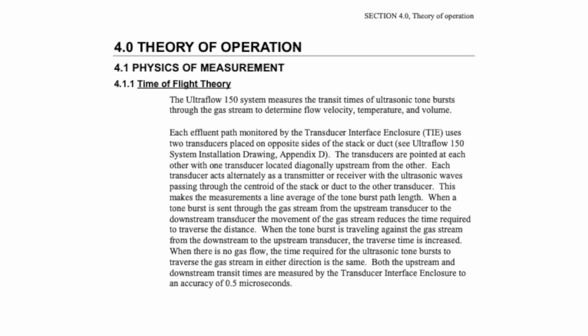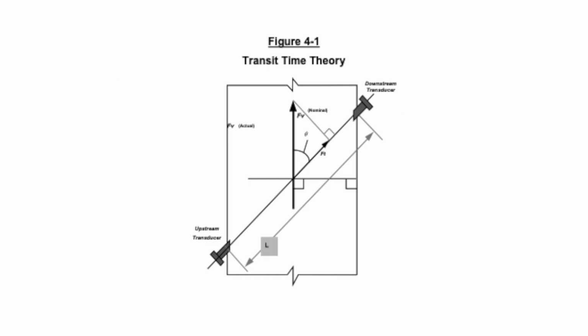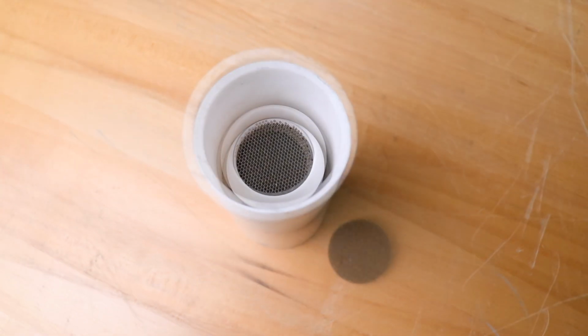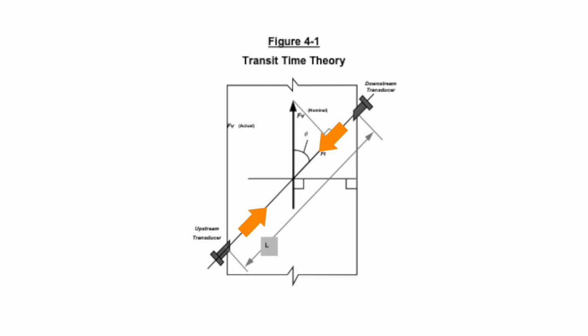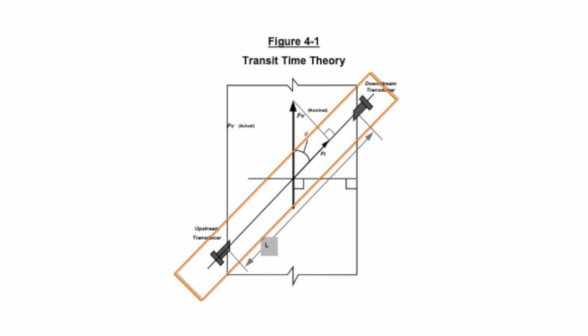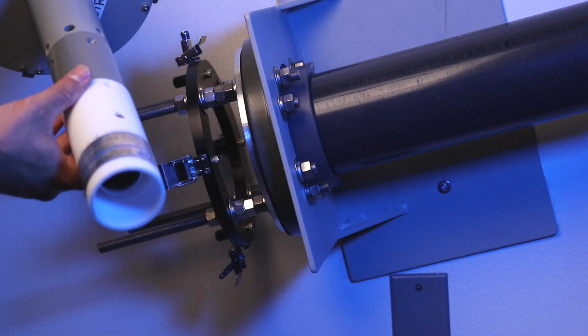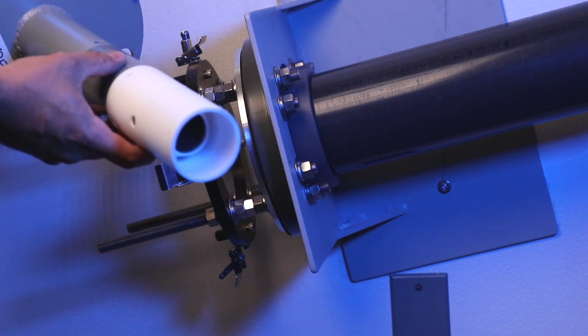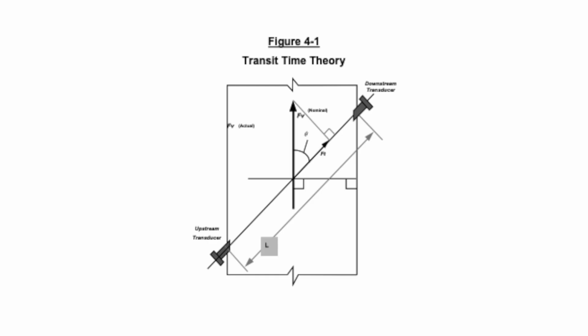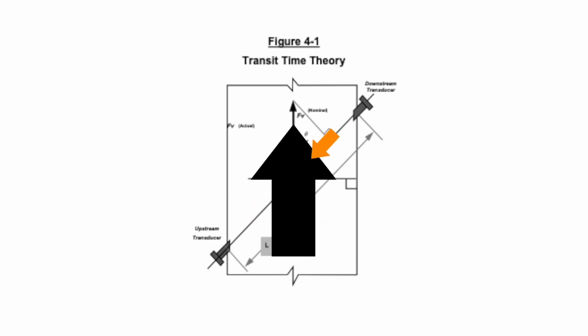The UF-150 works on the time of flight theory. Refer to Chapter 4 in your manual for a more in-depth description, but simply put, it measures the transit times of the ultrasonic tone bursts through the gas stream to determine the flow velocity, temperature, and volume. Each TIE uses two transducers placed on opposite sides of the stack or duct. These transducers are located diagonally across from each other and act as a transmitter and receiver for the ultrasonic waves. The time for the burst to cross the path decreases when traveling with the stream and increases when traveling against it.